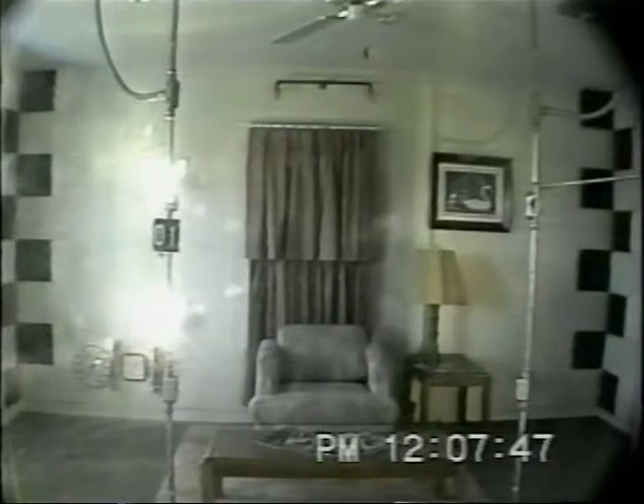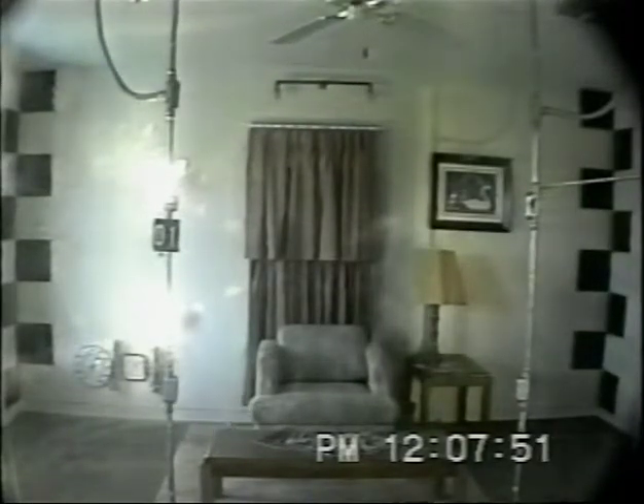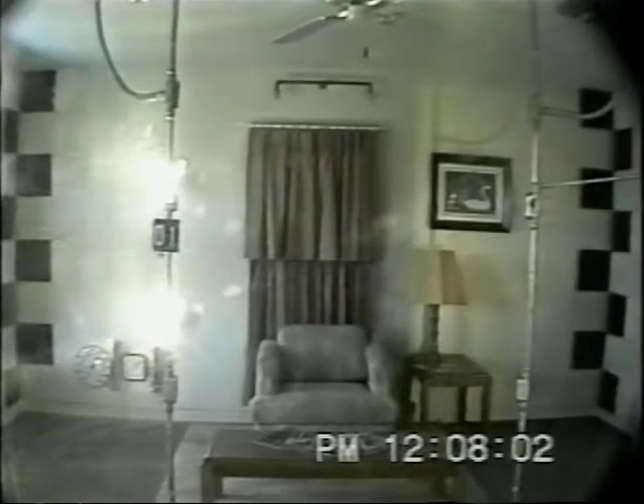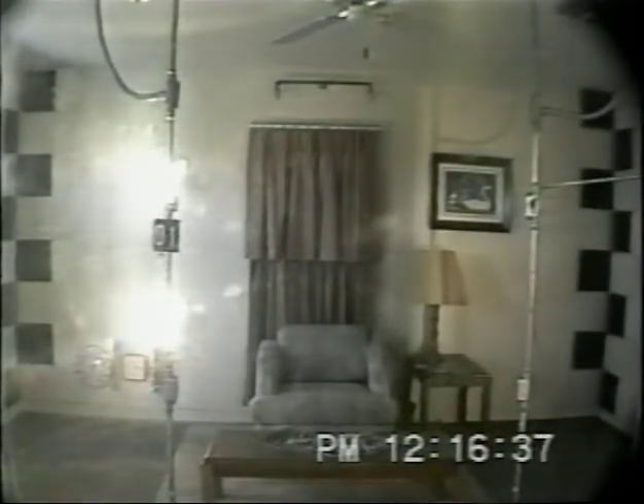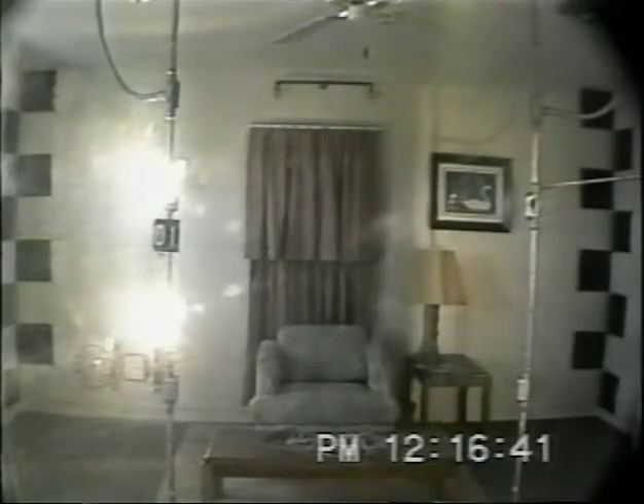The first fire scenario will simulate a smoldering ignition of a rayon cotton fabric chair. The heating element utilized will be rated at 602 degrees Fahrenheit. The heating element will be placed in the fold at the back of the cushion of the chair. This test will continue to the point where all of the fire detectors have activated. The various environmental conditions in the room of fire origin and in an adjacent hallway will be documented on the data logger and computer system.